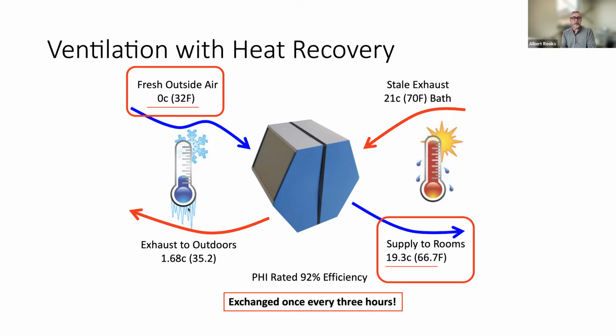And the side that has heat is going to give that heat to the side that has no heat, because nature is always seeking a balance. So if there's a high concentration of heat or moisture, opposite paired, and it's within a sensible proximity to a low concentration of temperature or humidity, nature's going to seek to balance and move some of that heat over onto the side that has no heat. And so essentially what happens with a heat exchanger, we'll see some examples of relative increasing efficiency, is we just manipulate the flow and the length of flow, or the length of time that the two streams of air pass next to each other. And that's how we start recovering more and more heat.